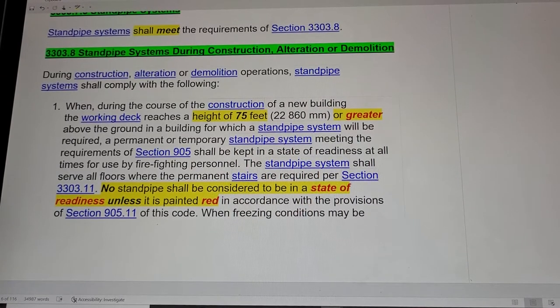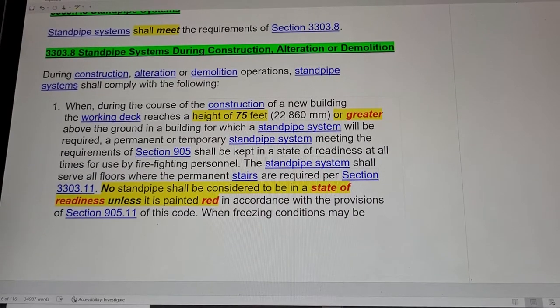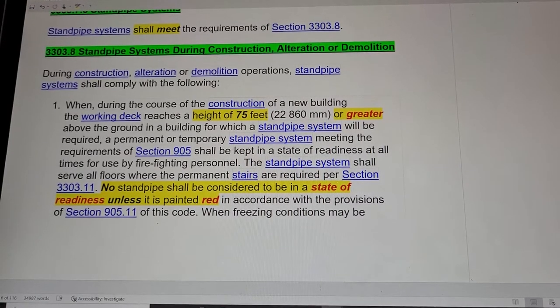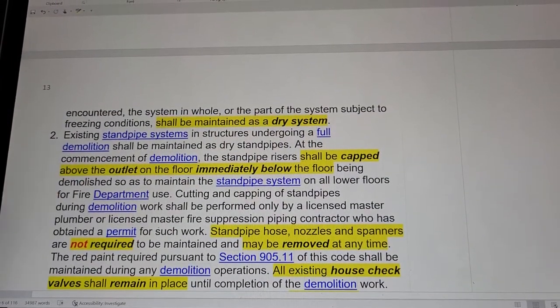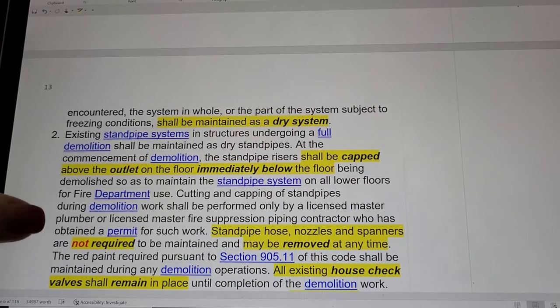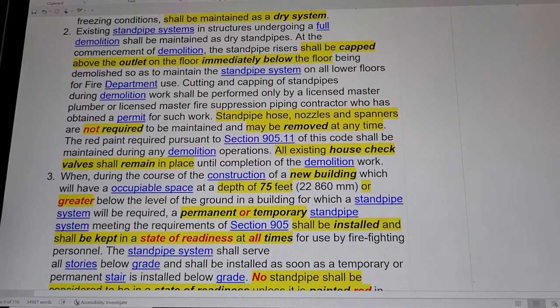The standpipe system shall be kept in a state of readiness at all times for use by firefighting personnel. The standpipe system shall serve all floors where permanent stairs are required per section 3303.11. No standpipe shall be considered to be in a state of readiness unless it is painted red. When the system in whole or in part is subject to freezing conditions, it shall be maintained as a dry system.